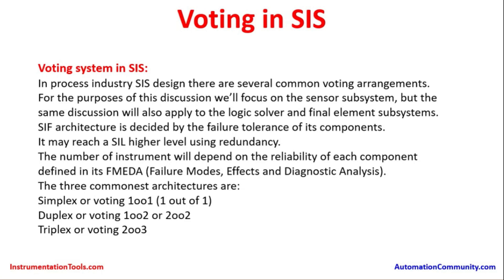These are the different subsystems that comprise a complete safety instrumented system, and whenever it is performing a particular function, it is known as a safety instrumented function. SIF architecture is decided by the failure tolerances of its components — it may be a sensor, a final element, a solenoid valve, a sensor failure, or any instrument or electronic card failure in the PLC. Using redundancy, it may reach a higher SIL level. The number of instruments will depend on the reliability of each component as defined in its FMEDA.